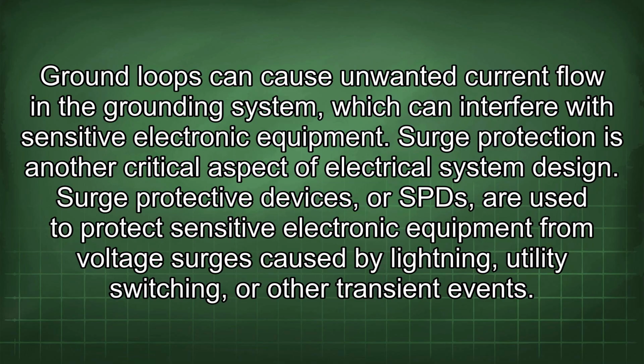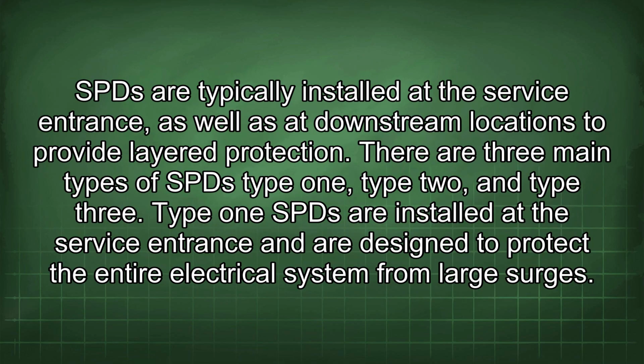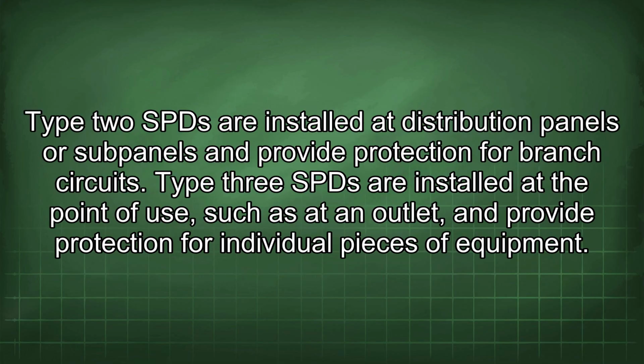or other transient events. SPDs are typically installed at the service entrance, as well as at downstream locations to provide layered protection. There are 3 main types of SPD: Type 1, Type 2, and Type 3. Type 1 SPDs are installed at the service entrance and are designed to protect the entire electrical system from large surges. Type 2 SPDs are installed at distribution panels or subpanels and provide protection for branch circuits.